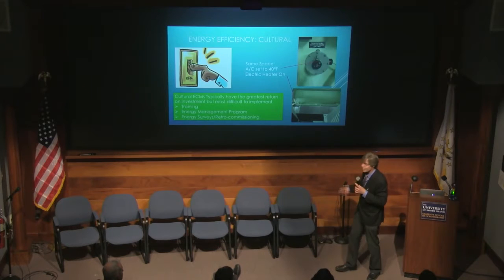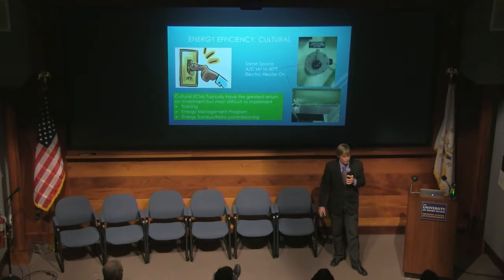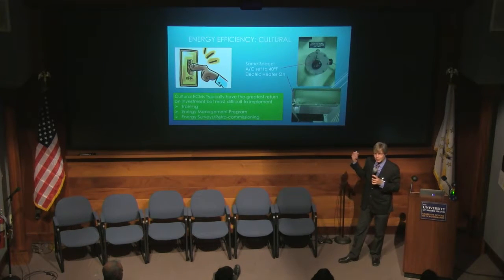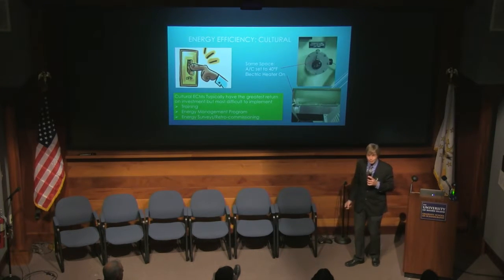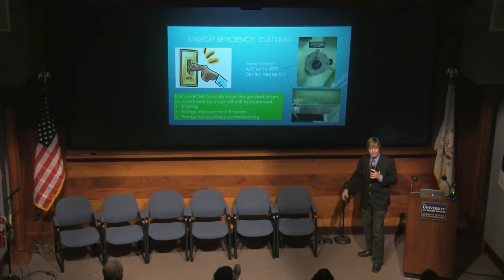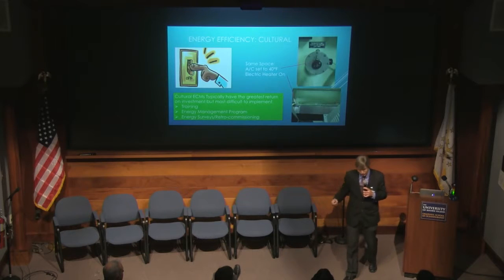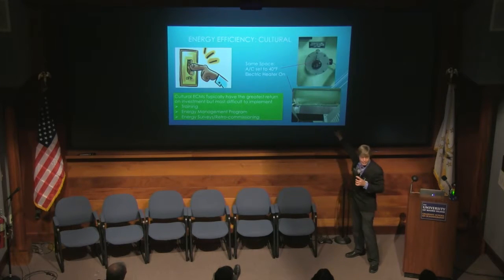So I go and find the air conditioning on the bridge set for 40 degrees, and the reheat's at 90. So when I decreased the capacity of the air handler, the reheat then took over and started to warm everything up. So instead of reducing the chill water temperature and increasing the air conditioning in the wintertime, I just went and turned the heat down.